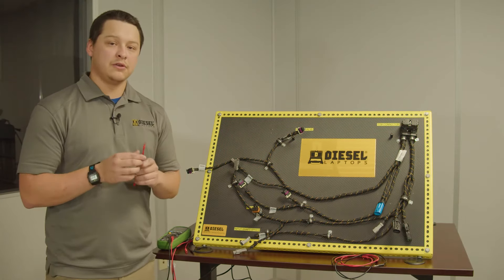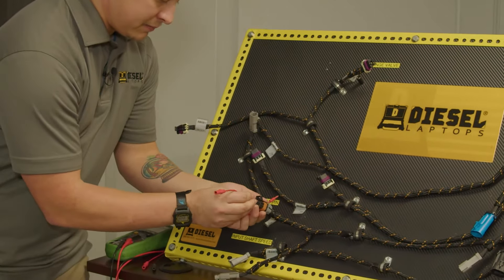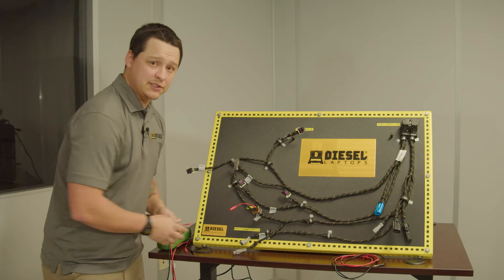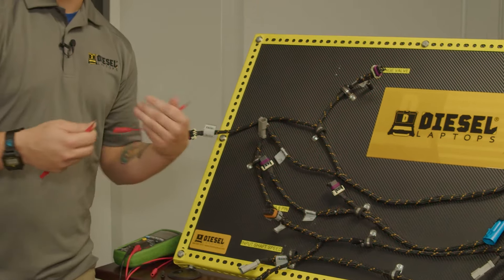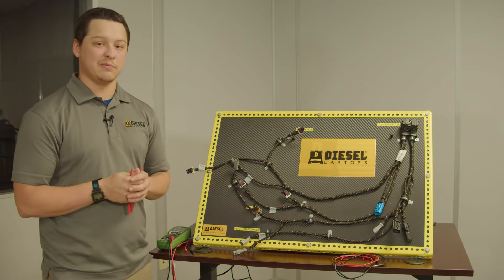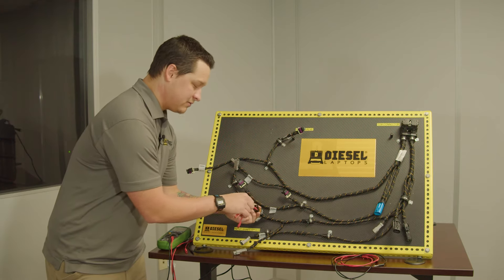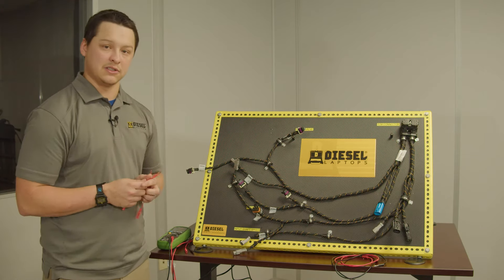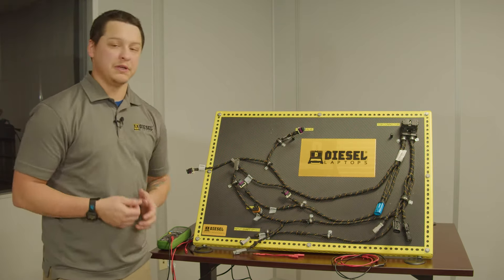When you plug in your proper test lead into the pin, you'll get slight resistance as you plug it in. When you pull it out you should also get a similar slight resistance. If you plug it into a pin terminal that's spread too far open or there's no tension on the pin terminal at all, it'll just slide right in with no resistance and come right back out with no resistance. At this point we know that we need to replace this pin terminal.